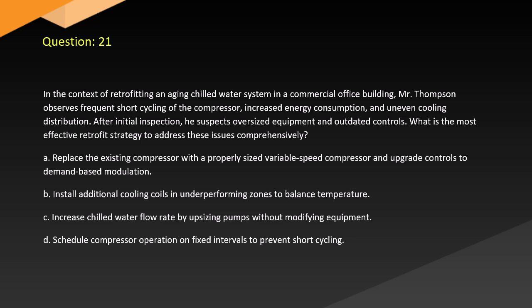A. Replace the existing compressor with a properly sized variable speed compressor and upgrade controls to demand-based modulation. B. Install additional cooling coils in underperforming zones to balance temperature. C. Increase chilled water flow rate by upsizing pumps without modifying equipment. D. Schedule compressor operation on fixed intervals to prevent short cycling.